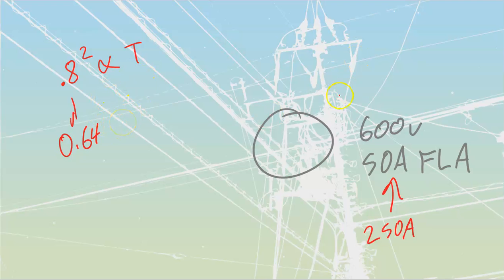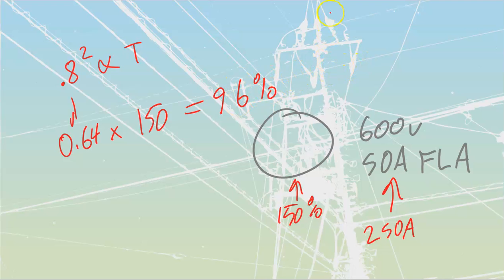Well, if we go back to the question, we found that the initial starting torque was 150%. So I'm going to take 64% of 150. 0.64 times 150, because that's my startup torque, calculates out to tell me that at the instant of startup, under an 80% reduction, I'm looking at 96% of my full load torque. This is pretty good, right?